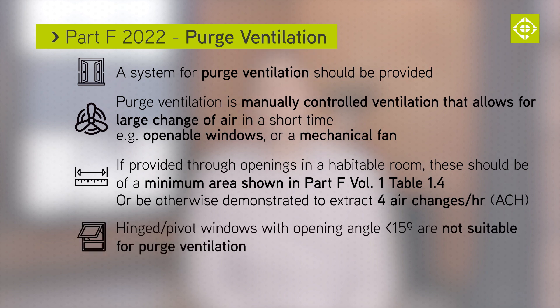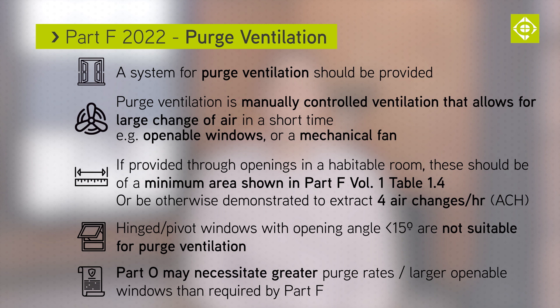Hinged or pivot windows with an opening angle of less than 15 degrees are not suitable for purge ventilation. Reference is also made to Part O of the building regulations, which is likely to require higher purge ventilation rates and larger opening windows than detailed within Table 1.4.